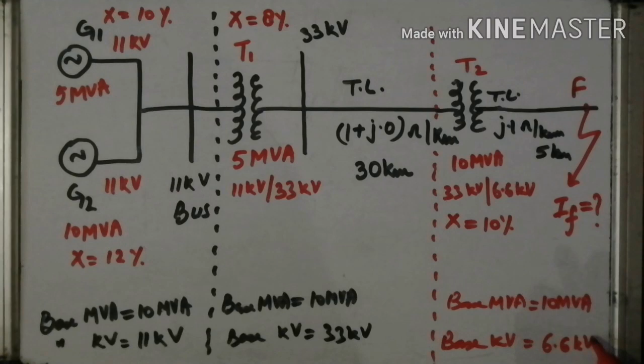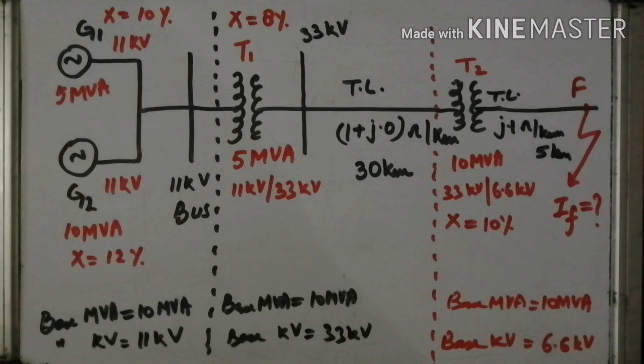This one is the step down transformer having the voltage ratio 33 kV to 6.6 kV. Okay, these are the base MVA rating, which is same, that is 10 MVA, and base kV is 11 kV, 33 kV and 6.6 kV. Now see the diagram very carefully. This one is the transformer number 1, this one is the transformer number 2. Its reactance is over here and its reactance is over here. Now I'm going to draw the diagram in per unit system.